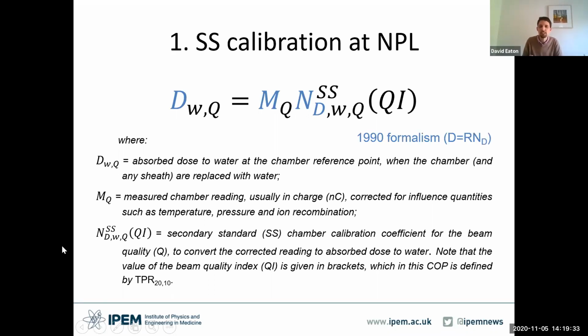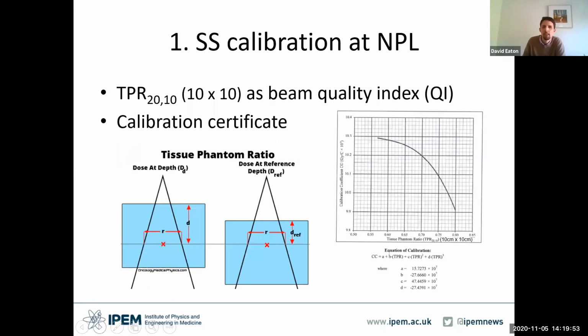Now you see that the 1990 formalism is still hidden in there. We have D equals RND, which is the 1990 code. We've changed R to M in keeping with the IAEA practice, so M for measurement rather than R for reading. But it is still in there. We just added a bit more detail to describe what's going on. So as I mentioned, we're using TPR, so the ratio of readings taken at 20 centimeters and 10 centimeters deep in an isocentric setup for a 10 by 10 reference beam. So that is our standard beam quality index, and that is what the equation and the graph that you get from NPL refers to on your calibration certificate.